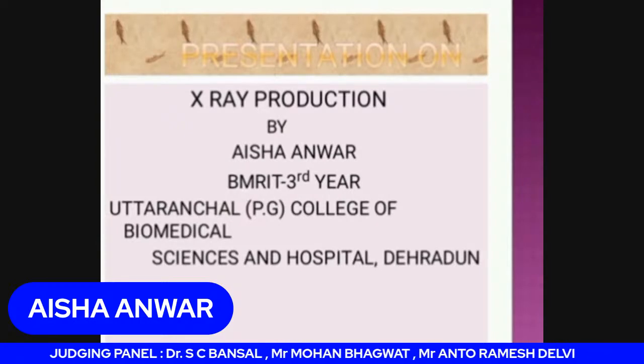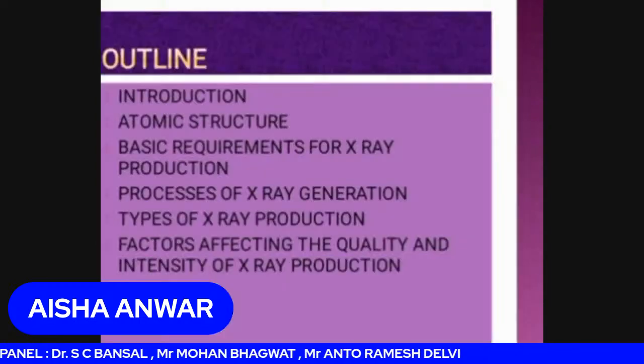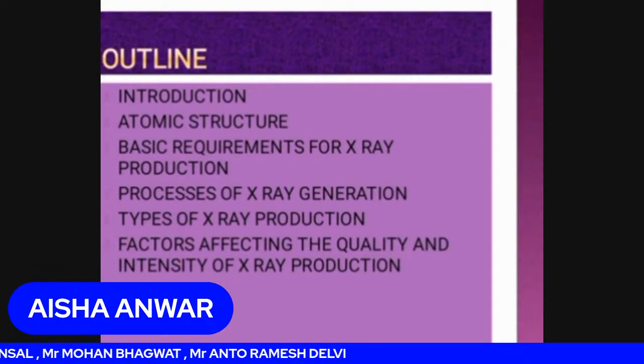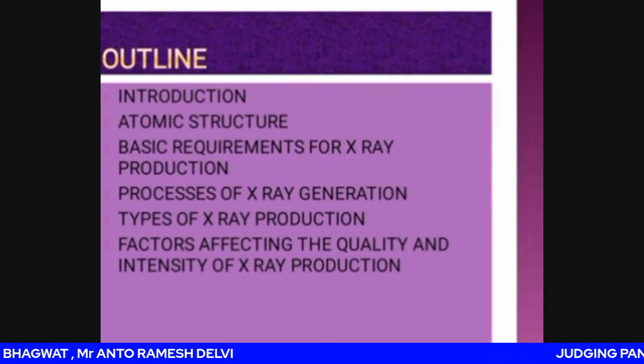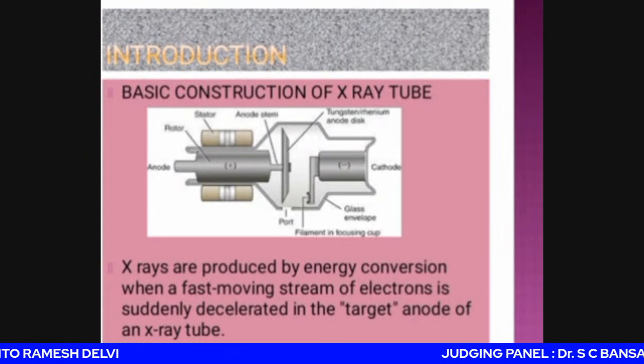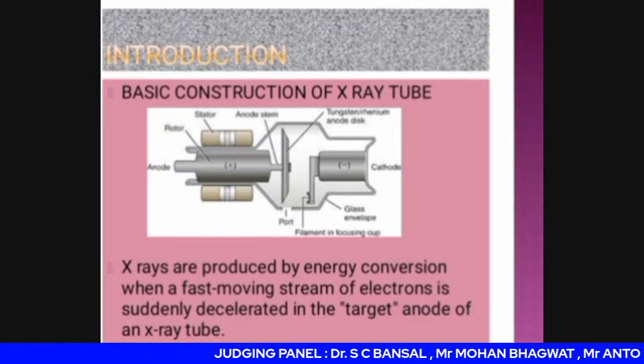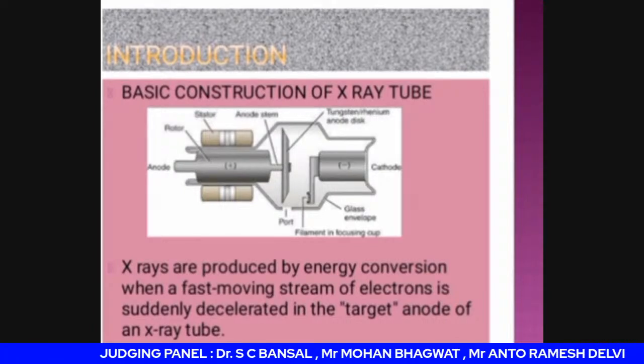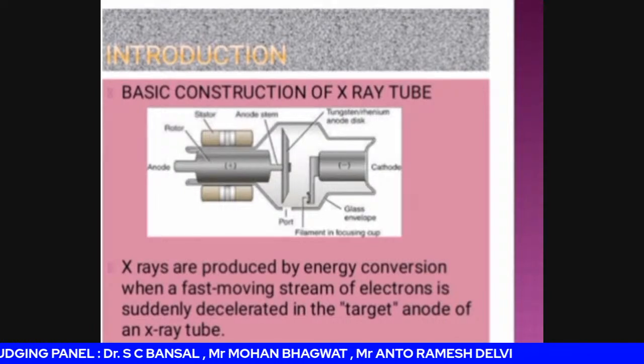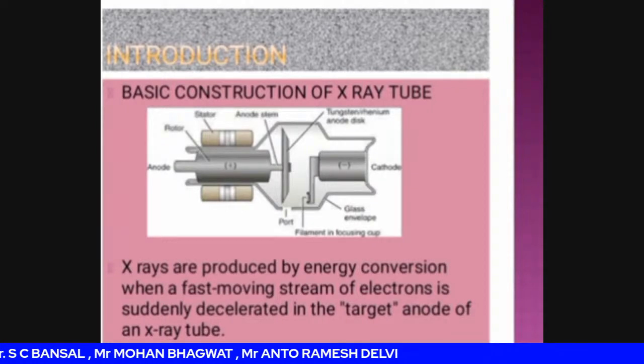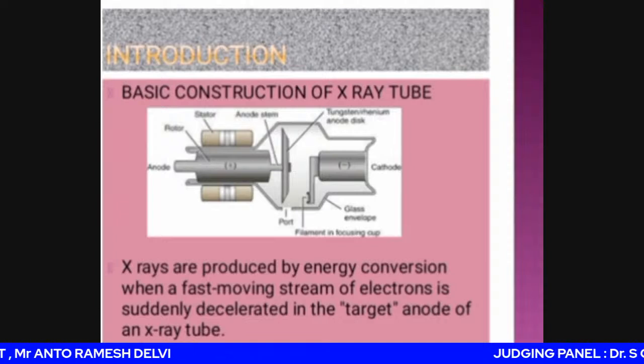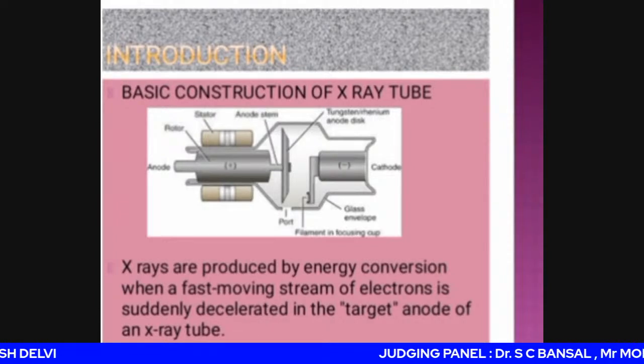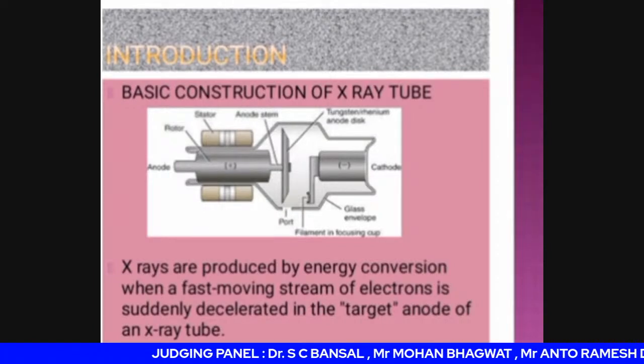Firstly, we should understand the basic construction of the X-ray tube. The X-ray tube is made up of pyrex glass that encloses a vacuum and contains two electrodes. The electrodes are designed so that electrons produced at the cathode can be accelerated by a high potential difference towards the anode. Electrons are produced by the heated tungsten filament and accelerated across the tube to hit the tungsten target where the X-rays are produced. Basically, the X-rays are produced by energy conversion when the fast-moving stream of electrons is suddenly decelerated in the target anode of the X-ray tube.